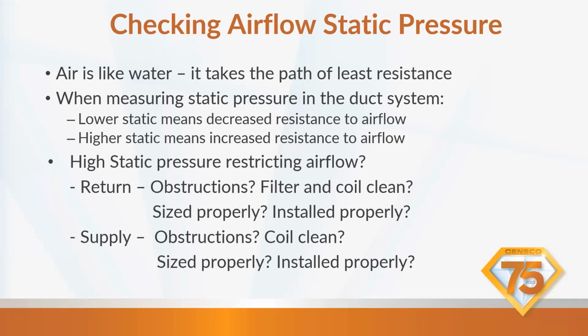Keep in mind, 1-inch filters are way more restrictive than 4-inch filters. A 1-inch filter doesn't have as much surface area as a 4-inch filter. So, of course, the MERV 13s and above are more restrictive than the MERV 8s. Are the filters installed properly? A 16 by 20 should not be on a 3-ton. We still see that a lot. That leads to high restriction where it's just like a hair dryer.